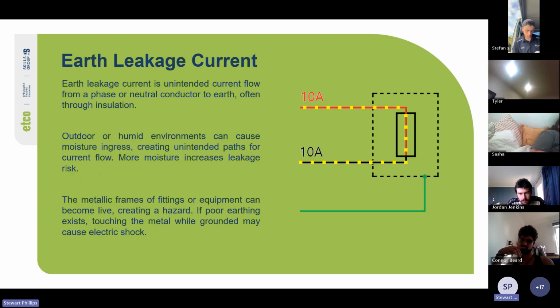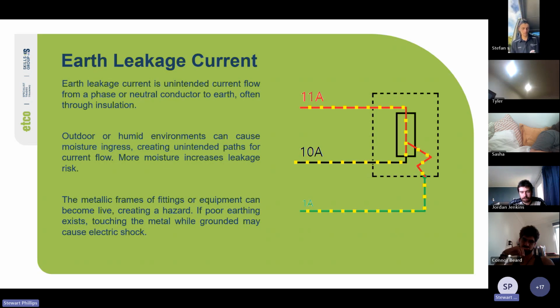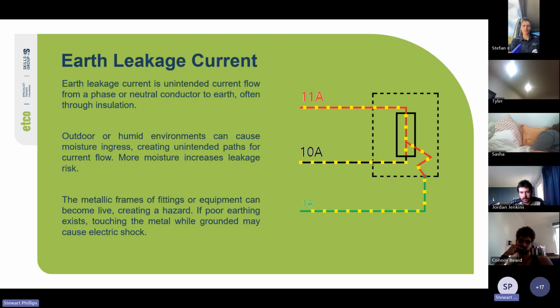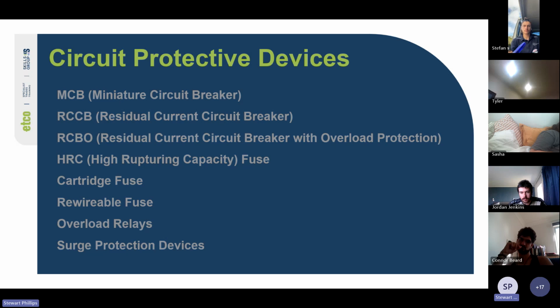And then when we talk about earth leakage, earth leakage current is unintended current flow from a phase or neutral conductor to earth, often through insulation. Outdoor or humid environments can cause moisture ingress, creating unintended paths for current flow. More moisture increases leakage risk. The metallic frames of fittings or equipment can become live, creating a hazard. If poor earthing exists, touching the metal while grounded may cause electric shock.